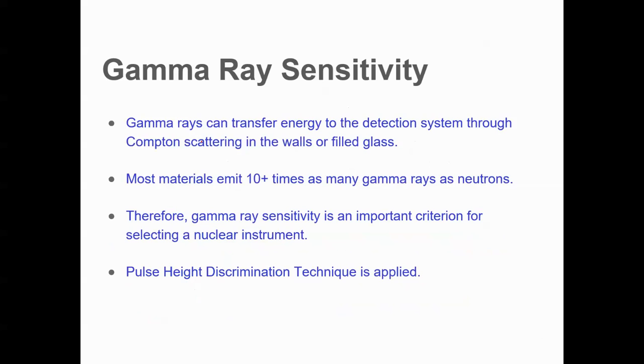So before discussing what is pulse height discrimination, we need to know what is gamma ray sensitivity. Gamma rays can transfer energy to the detection system through Compton scattering in the walls or filled glass. Most materials emit 10 plus times as many gamma rays as neutrons. Therefore, gamma ray sensitivity is an important criterion for selecting a nuclear instrument.